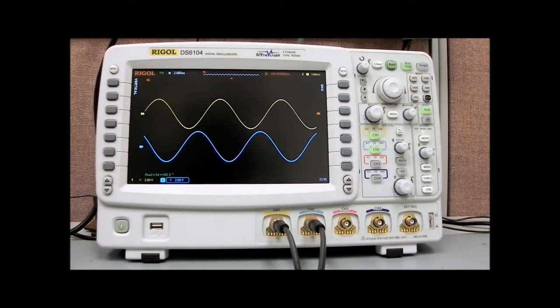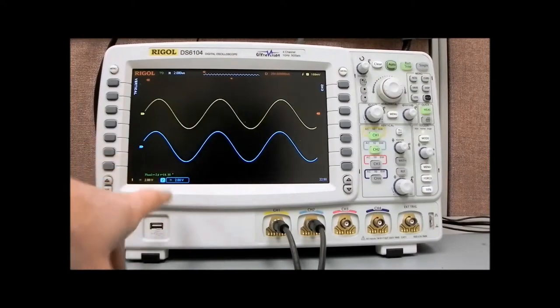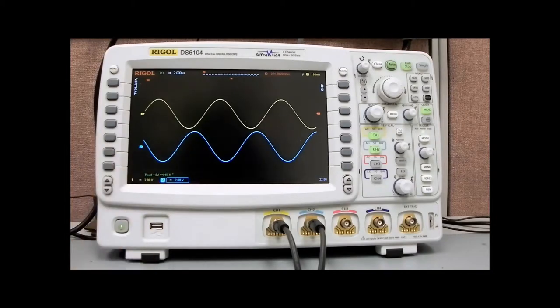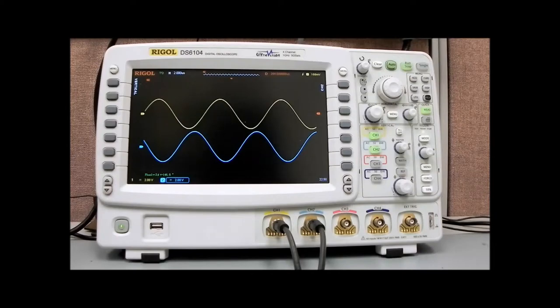Now I'm going to put in 11 degrees, and you'll see now we're making an automated phase measurement here. Let's do 186 degrees. And so we come up with, oh, I'm sorry, my function generator got angry. How about 145 degrees? So now we're at 145 degrees. So you can also use the automated measurement capability of the instrument, of the DS6000, in order to make those phase measurements between channels, which can be extremely useful as well.